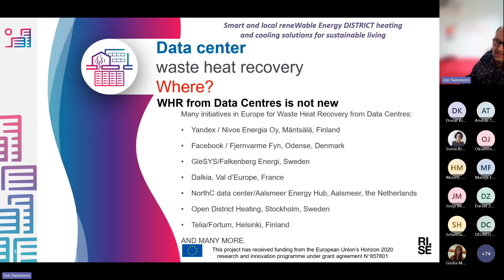This was taken from Facebook's sustainability report. Here they're talking about rejecting the heat from their data center, getting it into water or transferring it from air to liquid, then transporting it under the ground to the district heating substation, where the substation owns the heat pumps and upgrades it for distribution around the network.